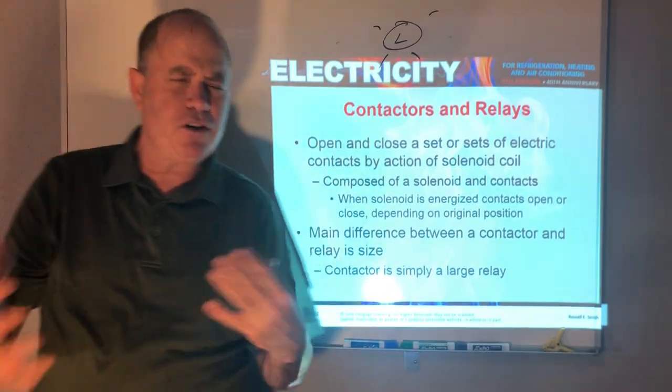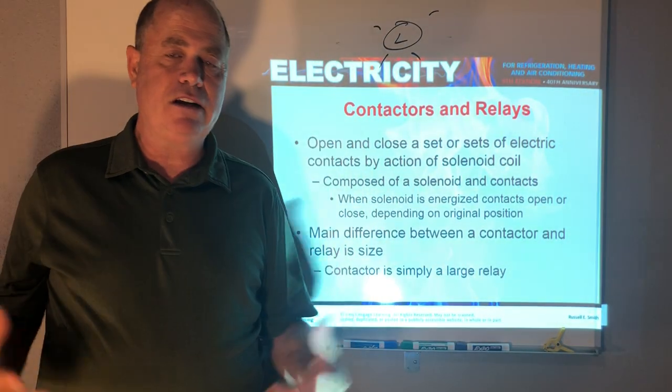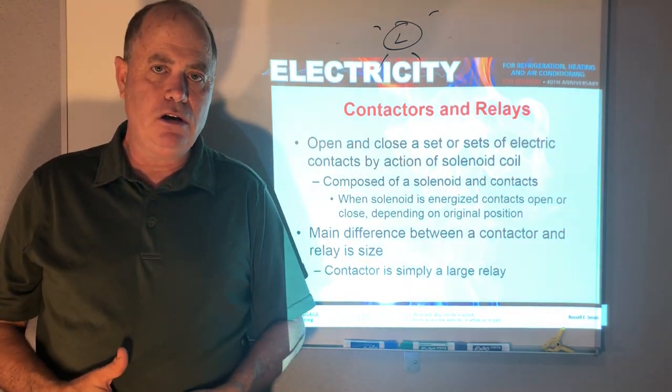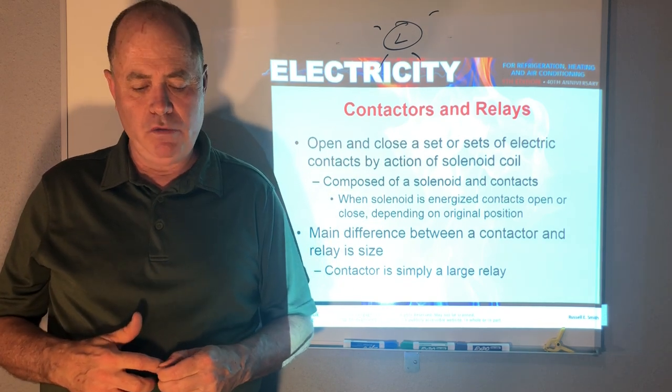And then basically the difference between a contactor and a relay is that a contactors for bigger electrical loads, usually over 15 amps and relays are for smaller electrical loads and the contacts are rated an amperage below 15 amps.